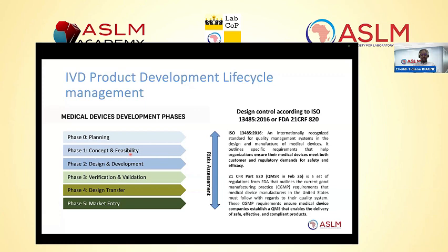And these design controls will allow you to ensure that the product that will be developed and put in the market will be safe, reliable, and will meet the performance standards. They follow the ISO 13485 standard, or, when it comes to Europe or other countries, or the FDA 21 CFR 820, and this is for FDA. These are quality management systems for different regions and different settings, but they share a similar goal.